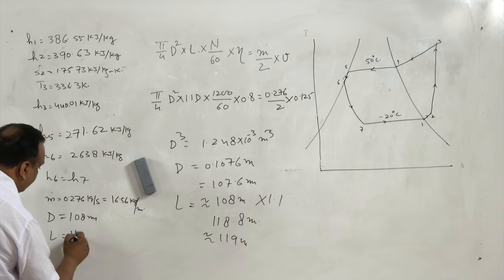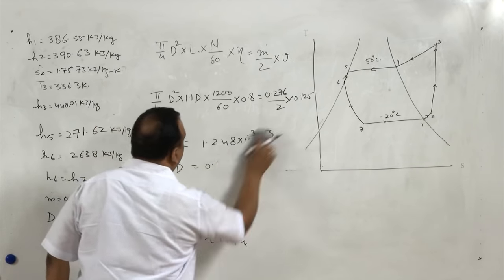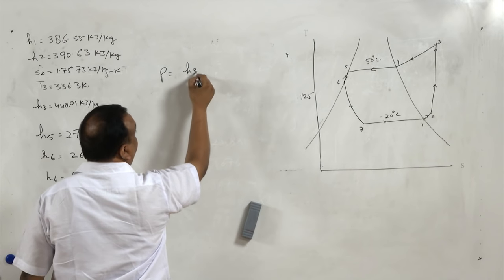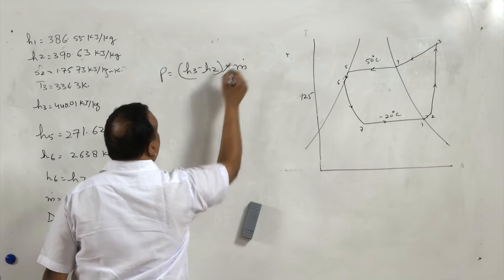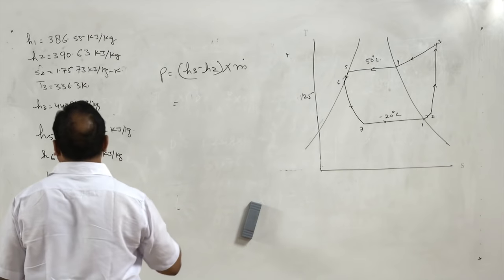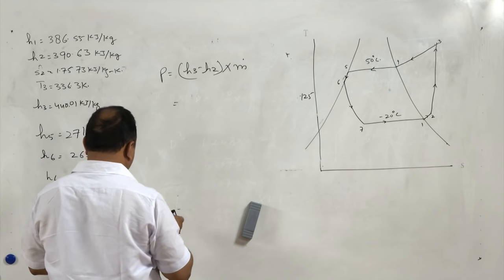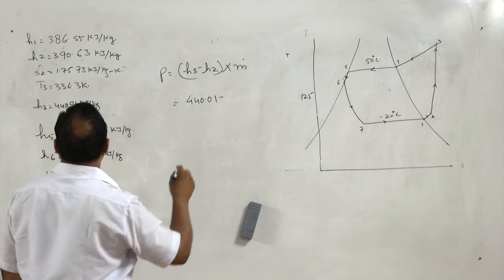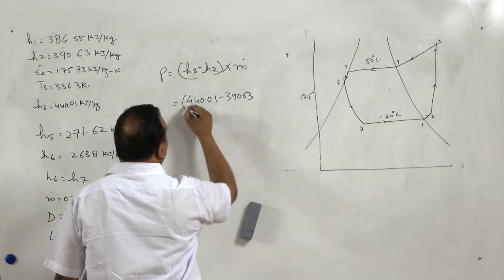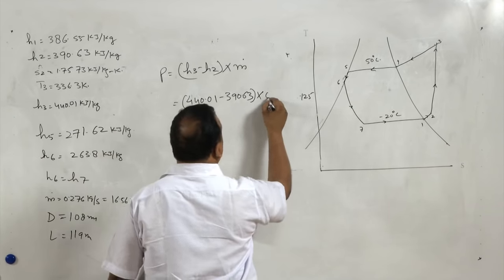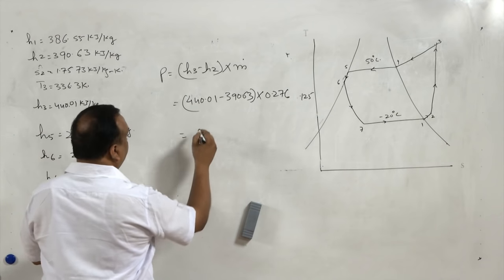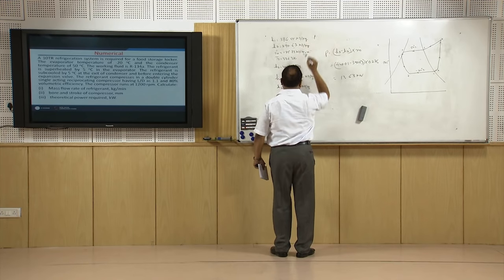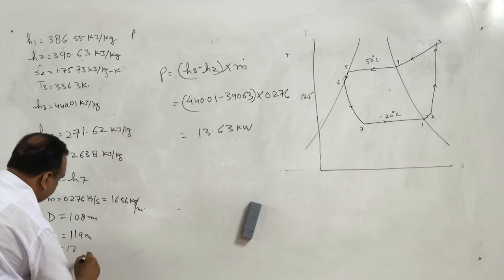The power consumed by the compressor is h3 minus h2 multiplied by the mass flow rate. With h3 equal to 440.01, h2 equal to 390.63, and mass flow rate equal to 0.276 kg per second, the power consumed by the compressor is 13.63 kilowatts.